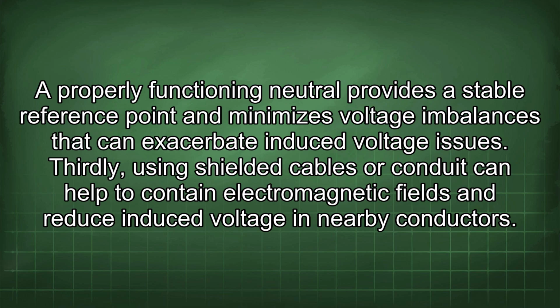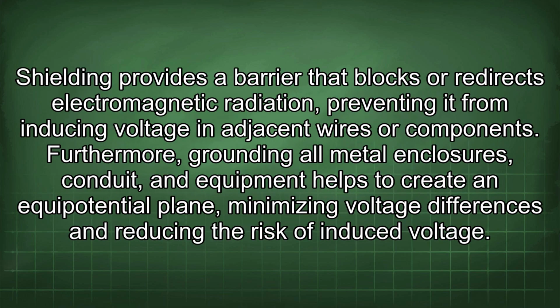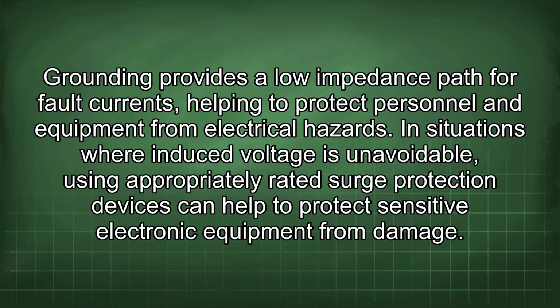Thirdly, using shielded cables or conduit can help to contain electromagnetic fields and reduce induced voltage in nearby conductors. Shielding provides a barrier that blocks or redirects electromagnetic radiation, preventing it from inducing voltage in adjacent wires or components. Furthermore, grounding all metal enclosures, conduit, and equipment helps to create an equipotential plane, minimizing voltage differences and reducing the risk of induced voltage. Grounding provides a low-impedance path for fault currents, helping to protect personnel and equipment from electrical hazards.